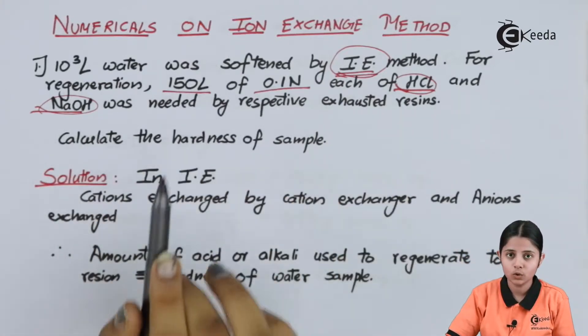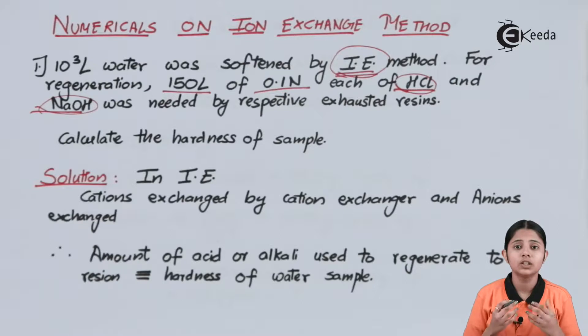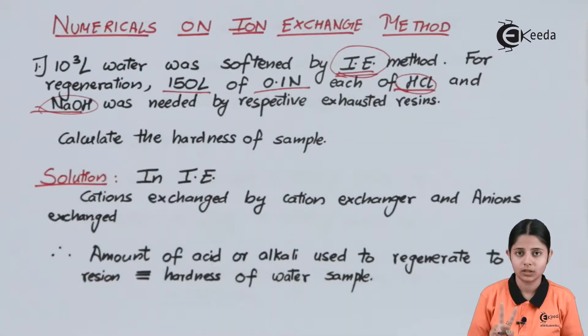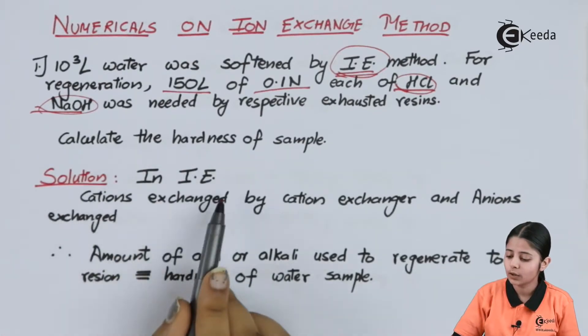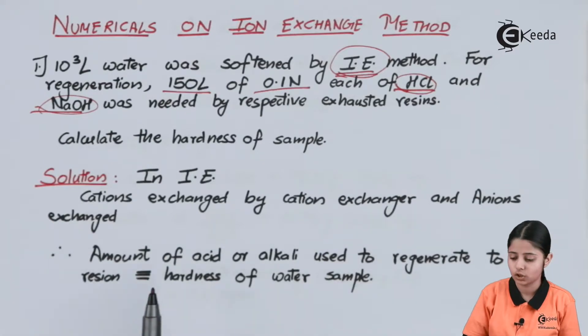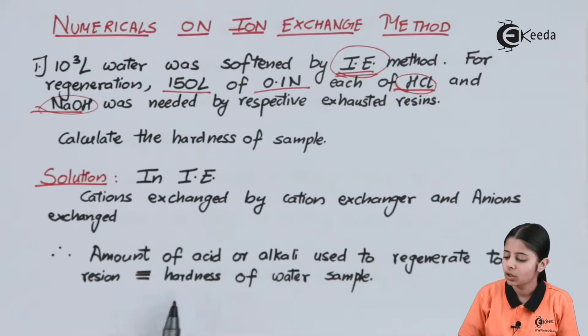The question here is about the regeneration of the resins in the ion exchange method. Both resins are there — cation resins and anion resins — and for both we will solve it. In ion exchange, cations are exchanged by cation exchangers and anions are exchanged by anion exchangers. The amount of acid or alkali used to regenerate the resin is directly proportional to, or corresponds to, the hardness of the water sample.